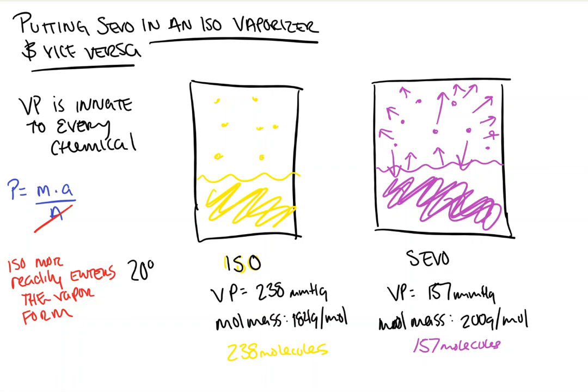So if we were to place isoflurane — which as a function of its chemical structure is more readily turned into a vapor — into the sevo tank, which is designed to try and liberate more molecules from something that is less likely to go from liquid to vapor, it means that we will overdose the patient. Because putting iso in a sevo vaporizer will lead to excessively more iso molecules being liberated than they would in a normal isoflurane container.